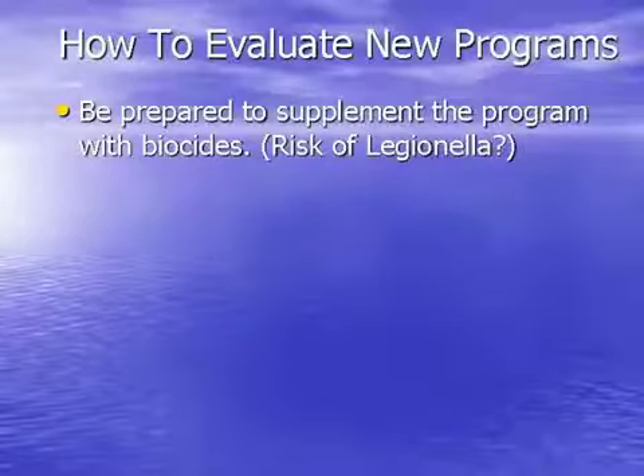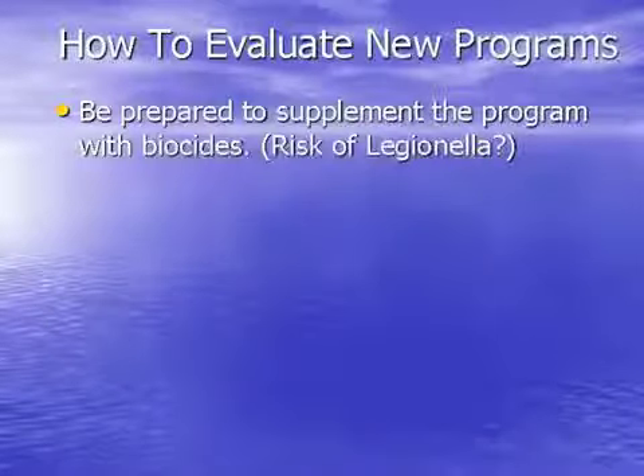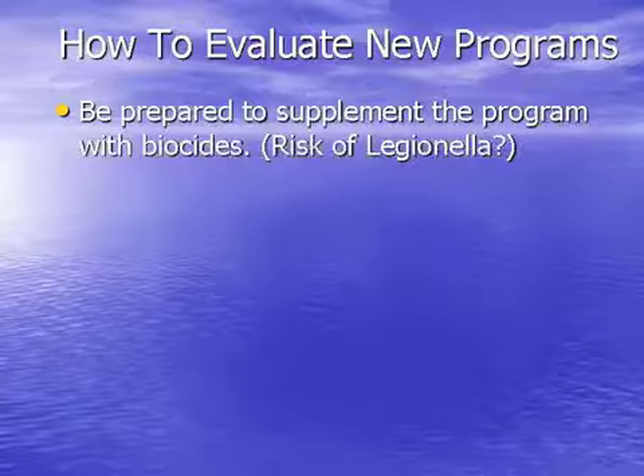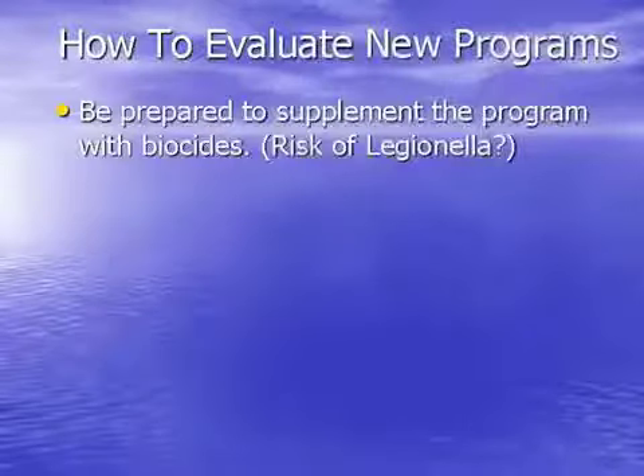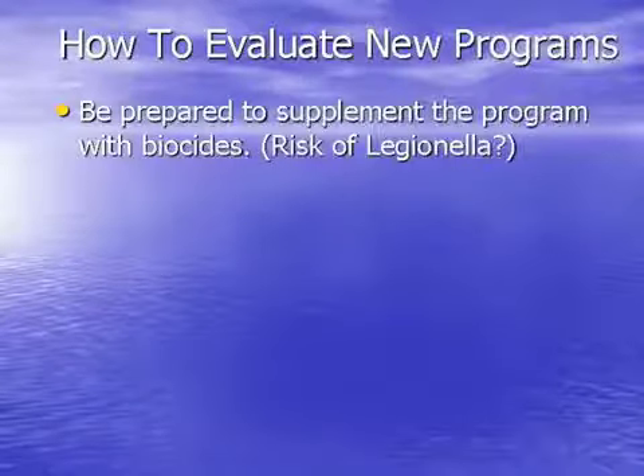The second thing is, be prepared to supplement the program with biocides. The number one driving force, with the exception of ozone, is basically biological activity. So you might want to be able to supplement with biocides and still be able to achieve your corrosion and scaling rates with these alternative devices. Don't necessarily shut them out if it doesn't work fully, but you might have to supplement that a little bit, and it still might be a great venture for your cooling systems.